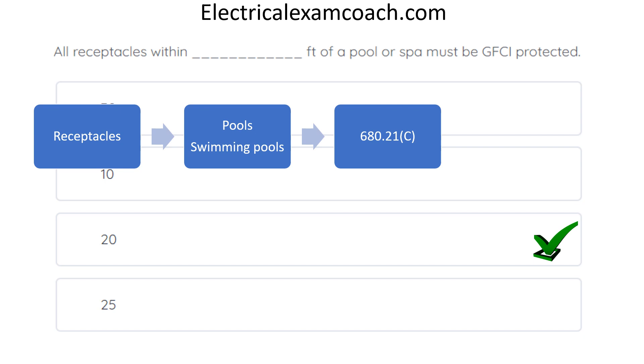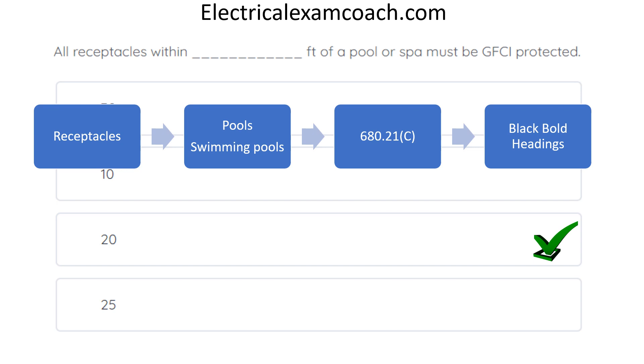We're in the right section, so we start reading the black bold headings to pull out keywords. We see 'circulation systems,' then 'other receptacles' — a keyword — and then 'GFCI protection' in a black bold heading. We read that paragraph and find, sure enough, 20 feet is the required distance. All receptacles within 20 feet of the pool or spa must be GFCI protected.